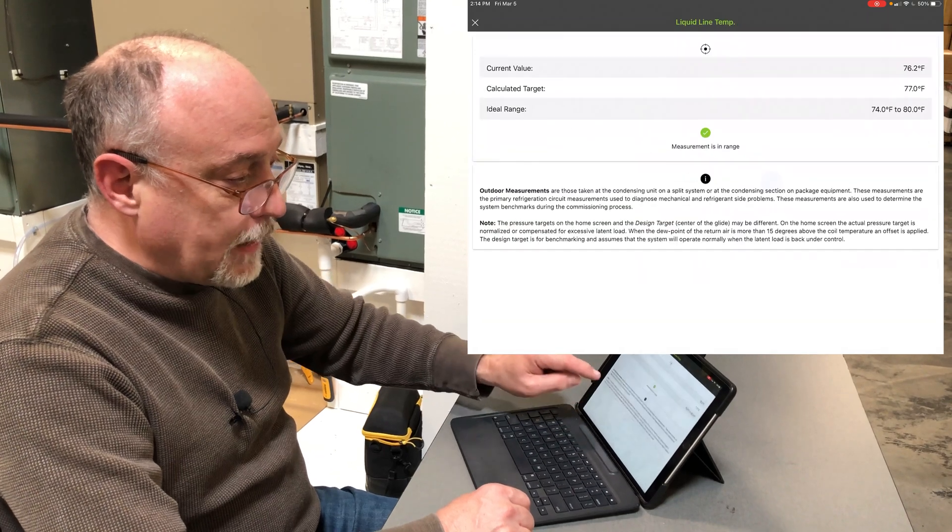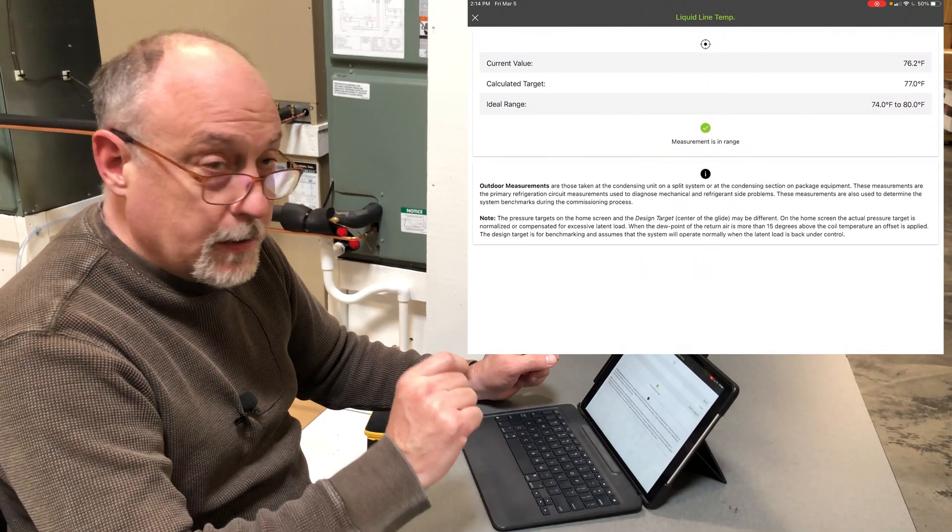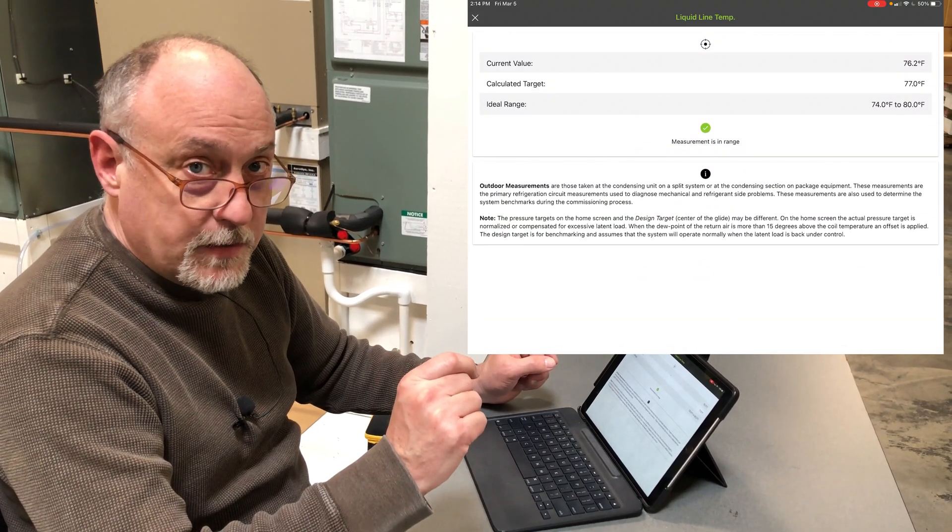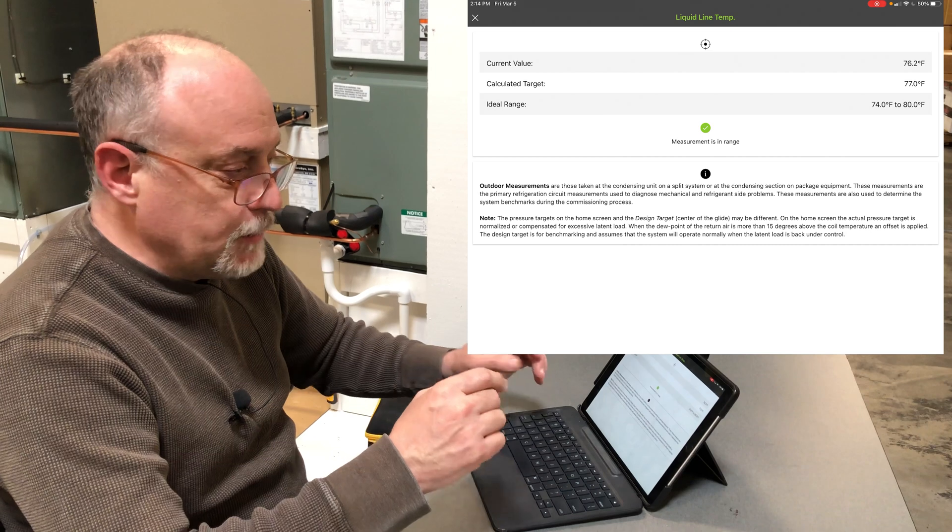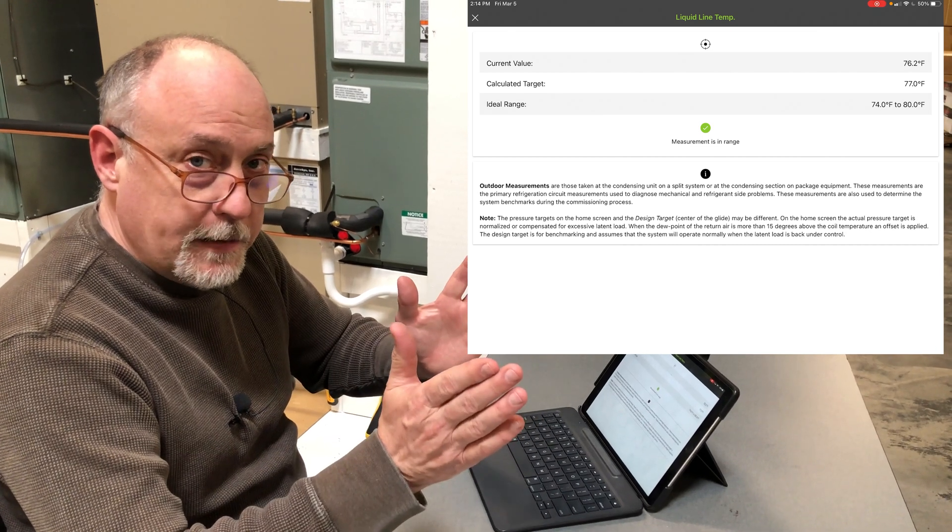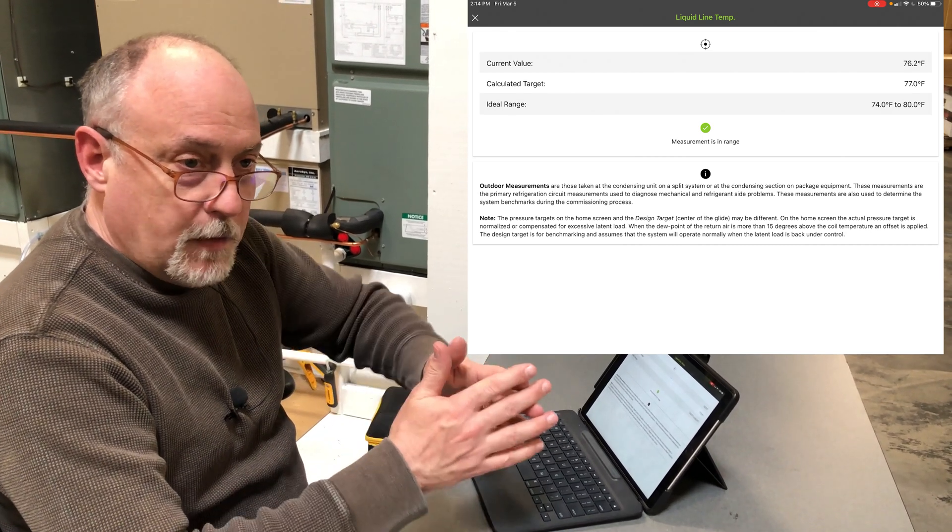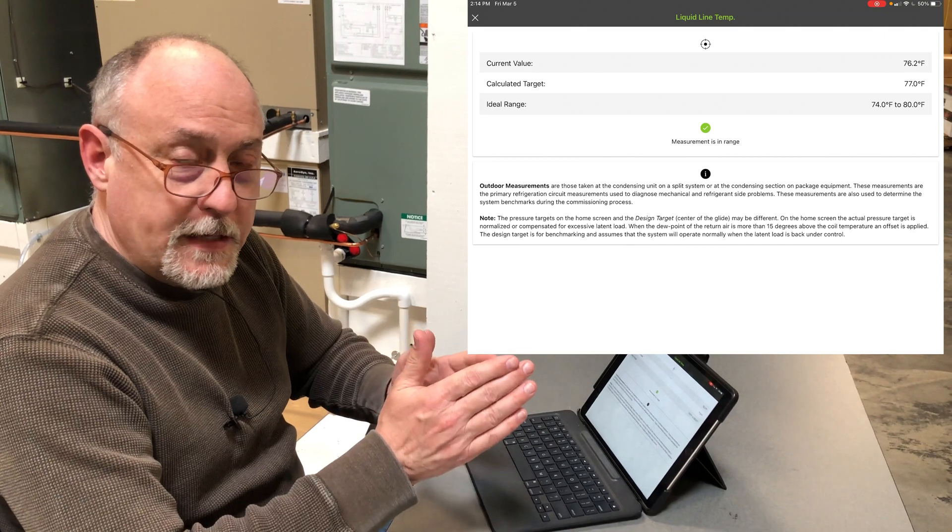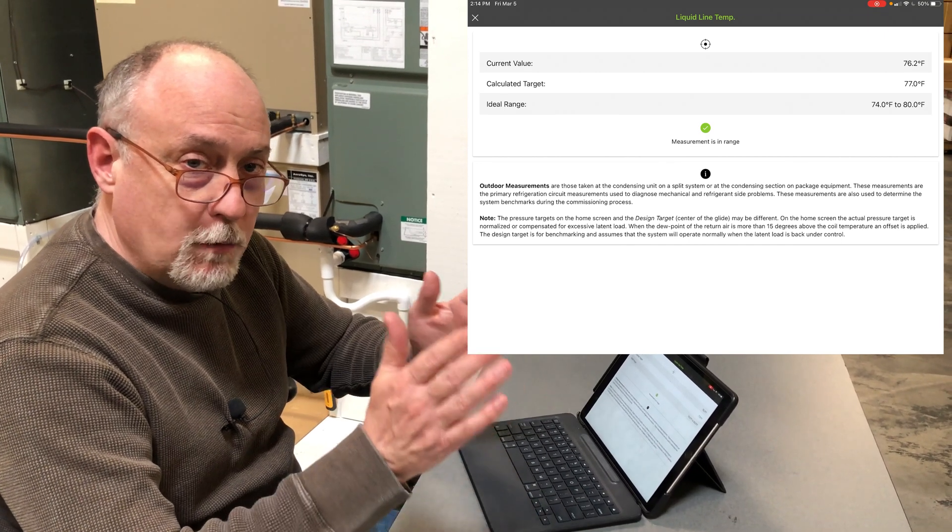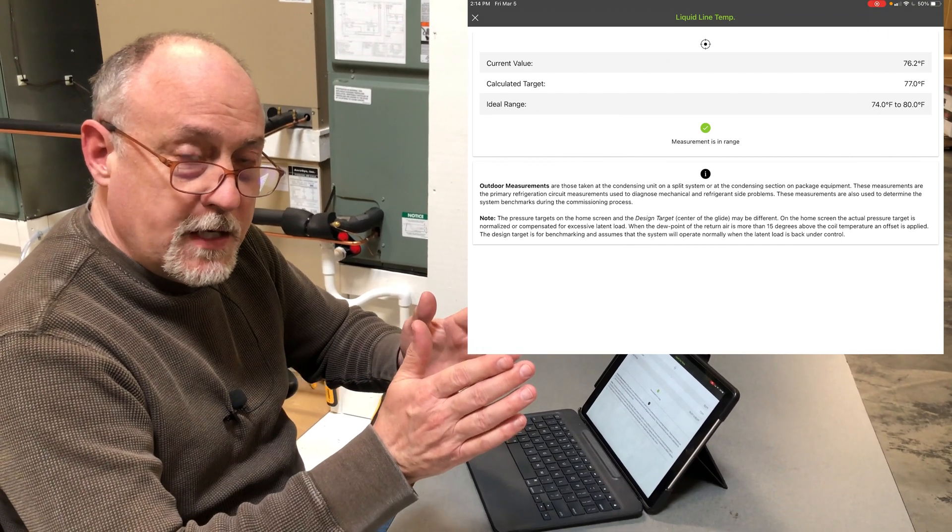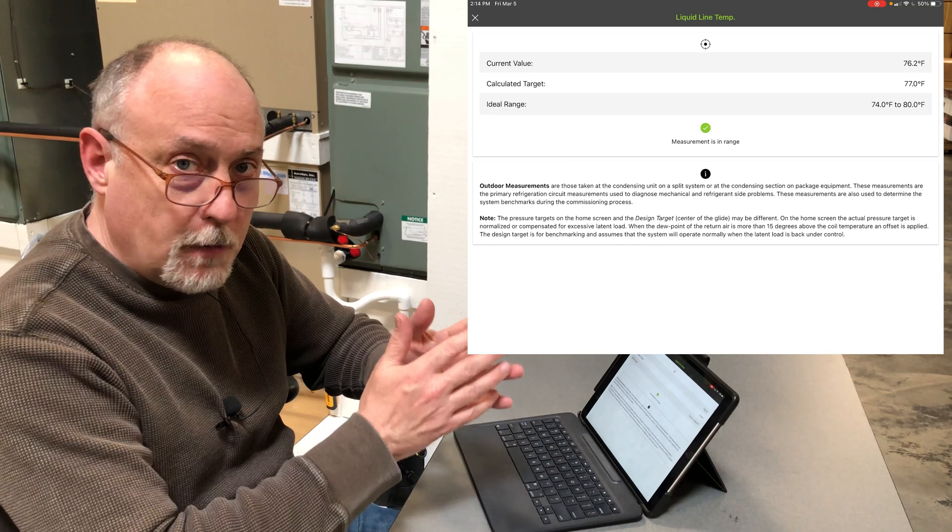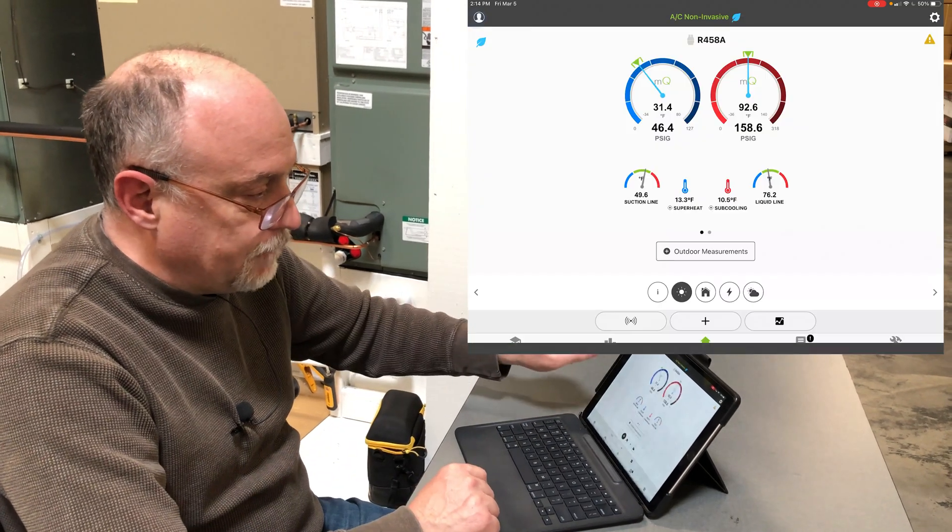It's looking for 6 to 24 degrees of superheat on the TXV would be acceptable. The liquid line for subcooling has a very tight target of plus or minus 3 degrees. The reason we have a wide range for the superheat is because you could have 100 feet of line set going through a hot attic one day and a cold attic the next. The superheat will vary because you can't control superheat after the bulb, and this is a total superheat calculation.